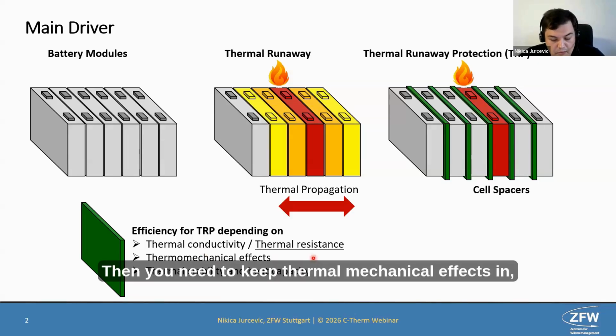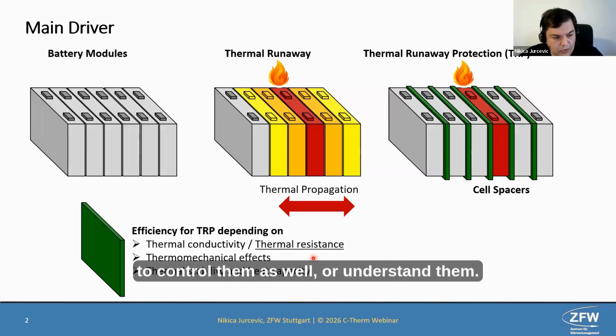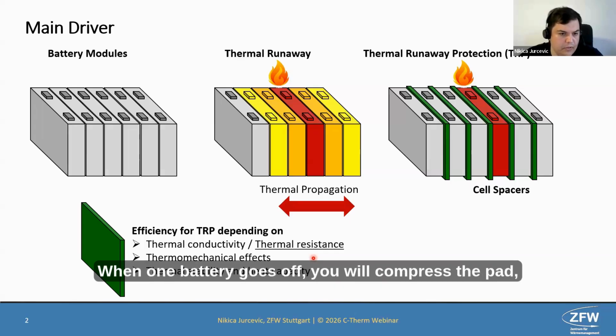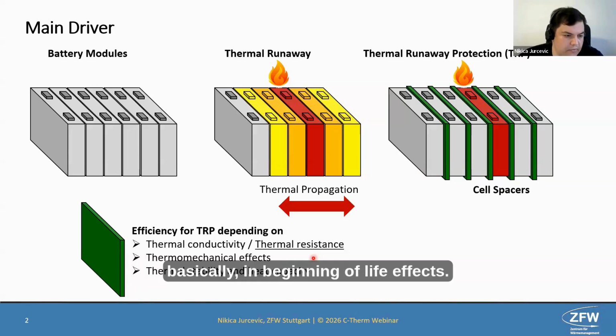Then you need to keep thermal mechanical effects under control, or understand them. So in this case, it's mostly the pressure. When one battery goes off, you will compress the pad and it might behave totally different than in the beginning of life effects.